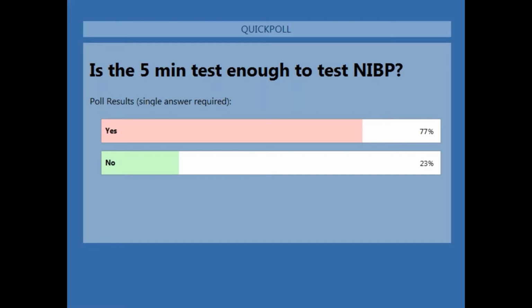The next thing that we want to verify is the safety relief in NIBP. That's what protects the patient from the NIBP pump in the patient monitor overpressurizing the cuff, making it too tight and painful, and actually possibly doing tissue damage if it's not able to be relieved. So we don't want that kind of a problem to happen during clinical use. So it's really important that we check the performance and safety of that safety relief valve for NIBP. So that would add to the amount of time that it takes.